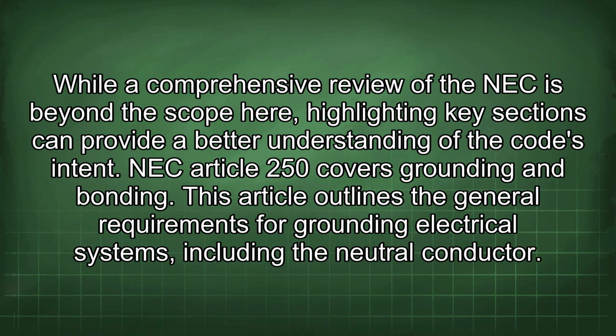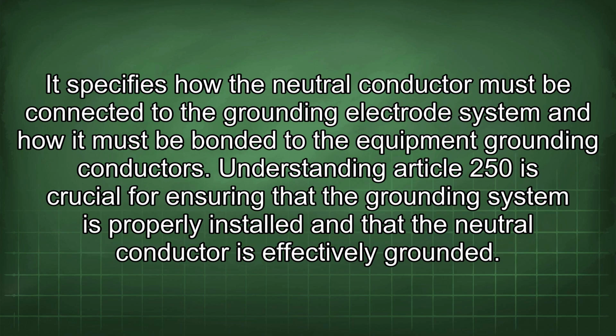While a comprehensive review of the NEC is beyond the scope here, highlighting key sections can provide a better understanding of the code's intent. NEC Article 250 covers grounding and bonding. This article outlines the general requirements for grounding electrical systems, including the neutral conductor. It specifies how the neutral conductor must be connected to the grounding electrode system and how it must be bonded to the equipment grounding conductors. Understanding Article 250 is crucial for ensuring that the grounding system is properly installed and that the neutral conductor is effectively grounded.